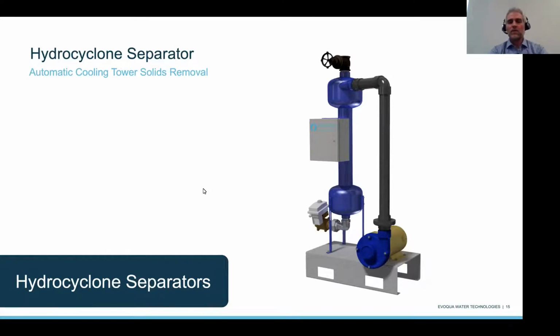A note on closed loops. Remember, closed loops can be quite significantly large, and depending upon the operation of your system, you could have a significant amount of dead legs of various different loads. So starting those loads up at various different frequencies can cause a lot of disturbance in that closed loop, kicking up quite a bit of dirt and debris and fine particulate in that closed loop. So yes, to Gary's point, don't forget about closed chilled loops. All right, so we're taking things off into some of the product solutions.